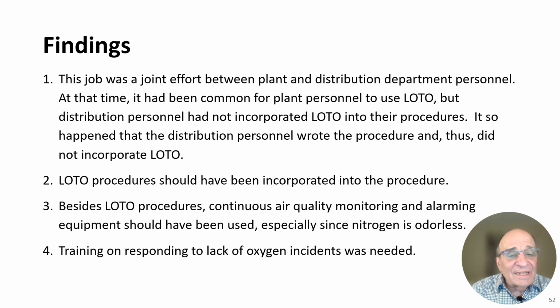Besides lockout and tagout procedure, continuous air quality monitoring and alarming equipment should have been used on this particular job, especially since nitrogen is odorless. You can't tell if nitrogen is coming into an opening. The air we breathe is 78% nitrogen. Training on responding to a lack of oxygen incident was needed and was not performed.